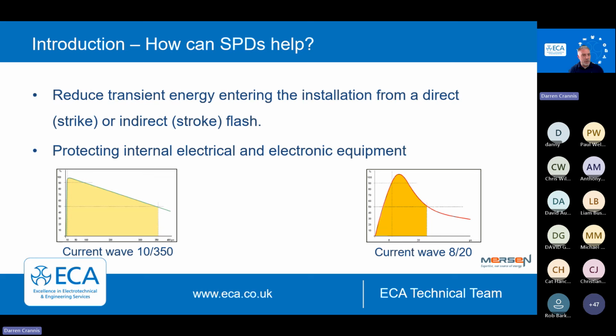And that's why if you look through the book, we like to call it the piano keys selection on there, but it tells us how to install those Type 1s. So when it comes to installing devices for lightning protection, that's absolutely our remit. And we get a bit of that guidance from 62305, and that's dropped into our Brown Book, and that helps us select and erect the right Type 1 SPD for that.